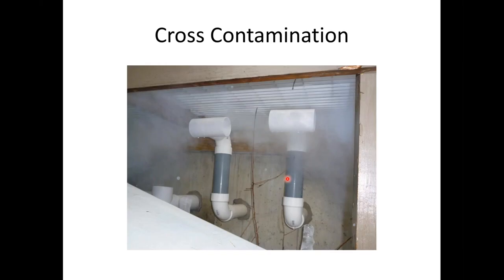This is the Philadelphia Housing Authority, and cross-contamination, a lot of things wrong here. We gave them the vent kits for the boilers, and you can see they used the CPVC first, the first things that were on there. Very, very fun. But these are things that you want to try and avoid. These are all worst case scenarios. And again, venting is usually one of the first things I suggest that you look at. A lot of times it's easier to move that boiler to an outside wall or where we're closer to get that vent there than try and run the 3-inch vent line across basements or through finished areas.